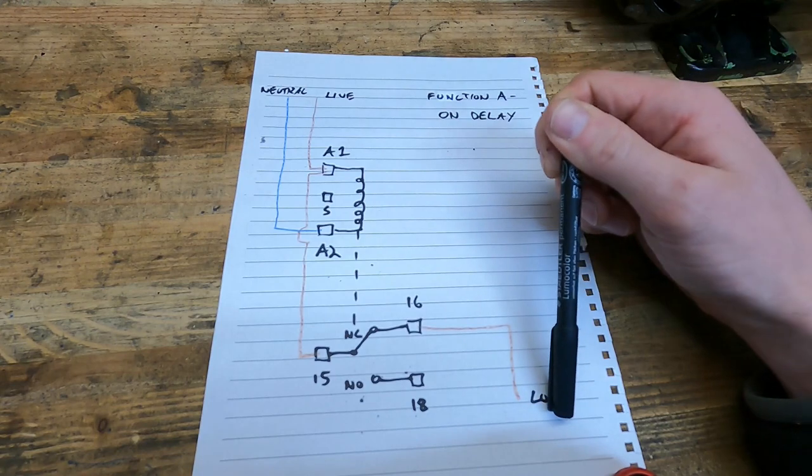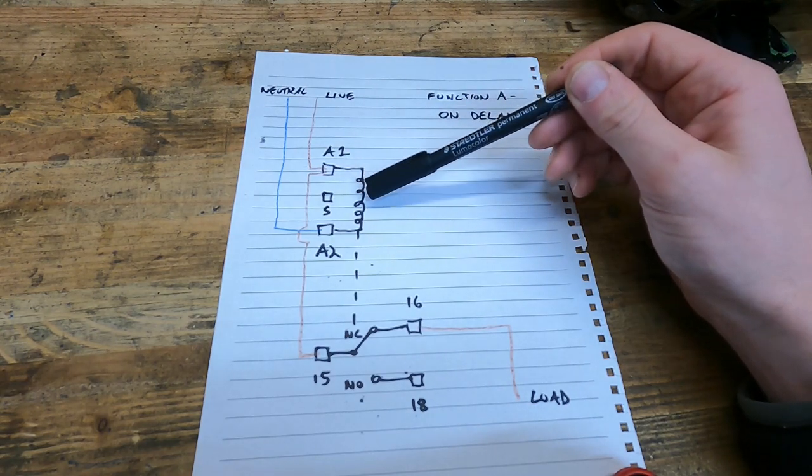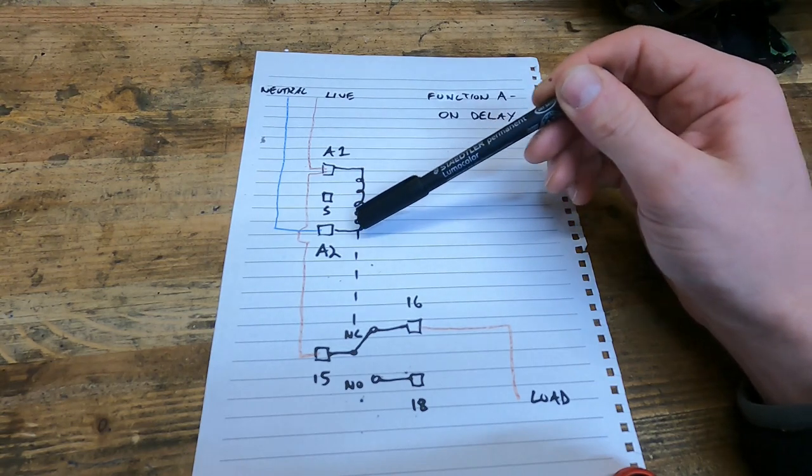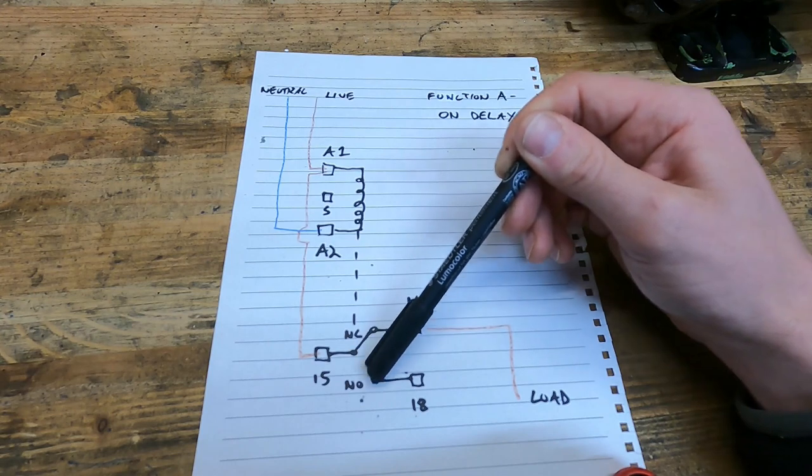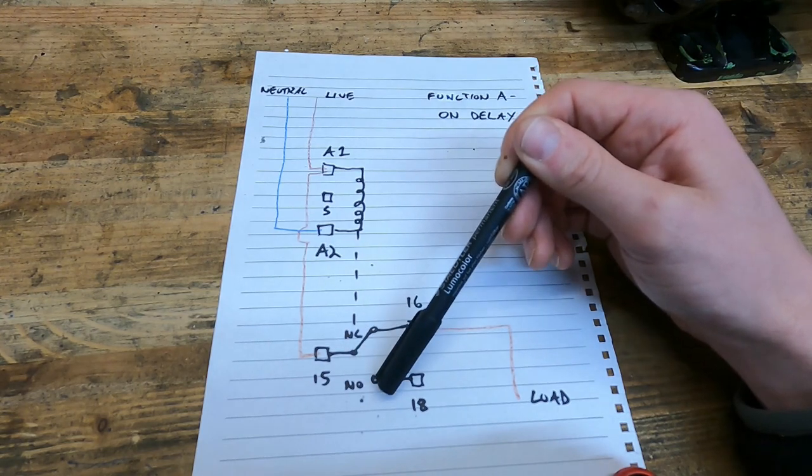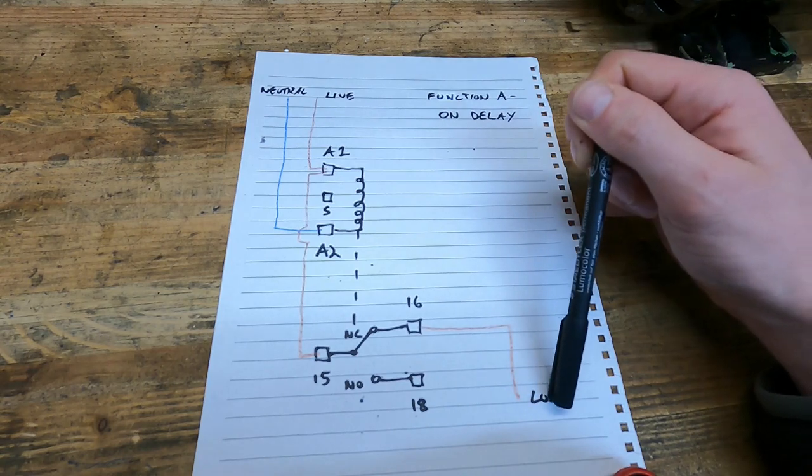We're going to be using terminal 16. So when power is applied to A1 and A2, power will also go through terminal 16 to the load. But then after the time period that we specify—and it's adjustable—the relay will actuate and this normally closed switch will become open and this normally open switch will become closed. So after that time period, no supply will go to the load.